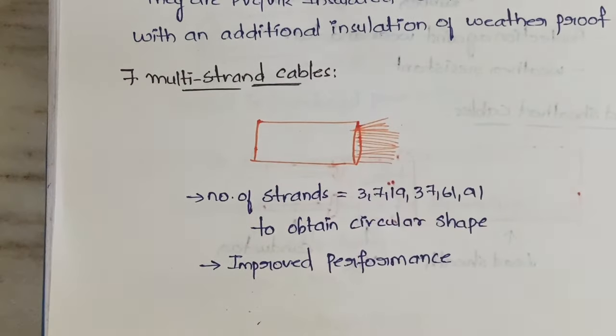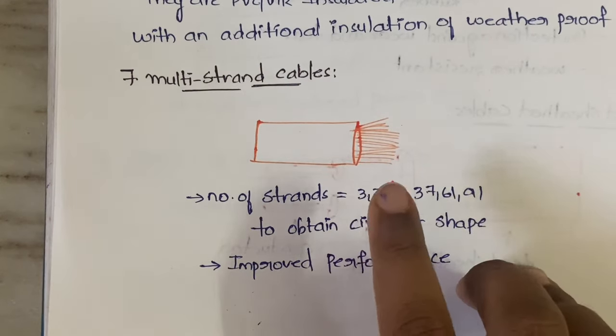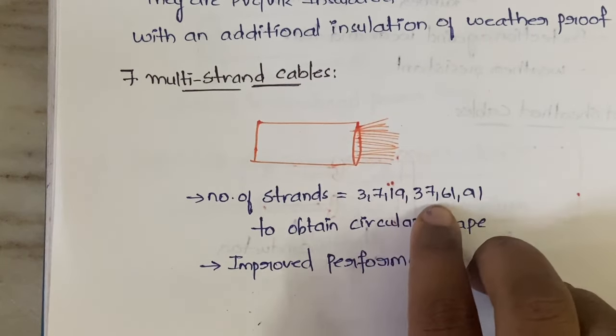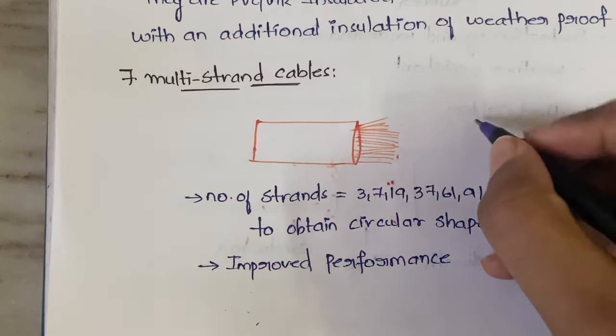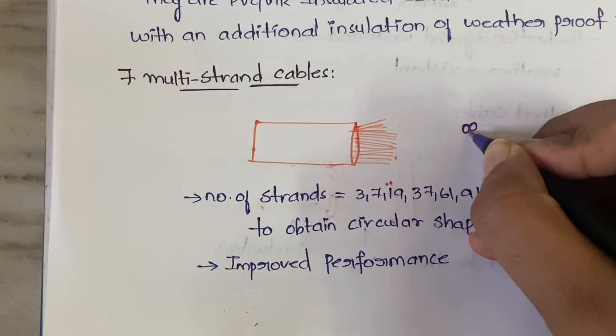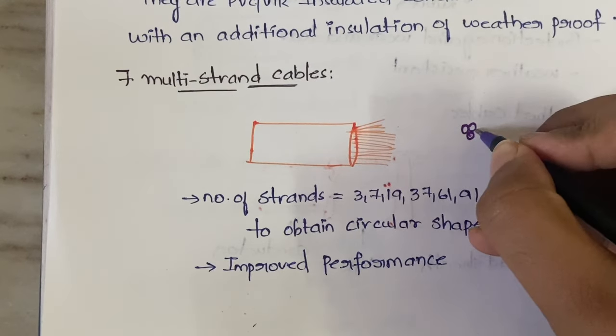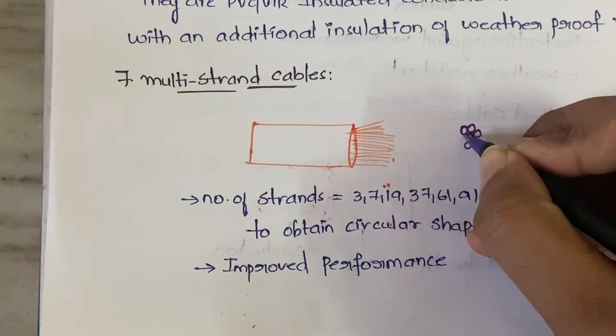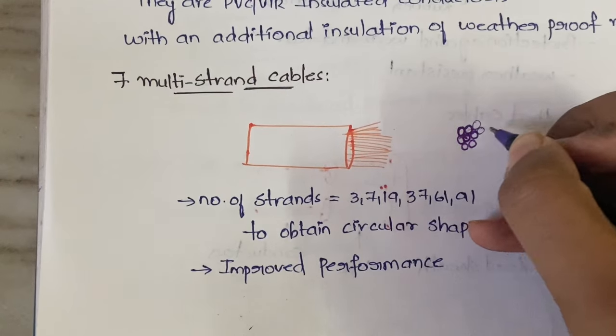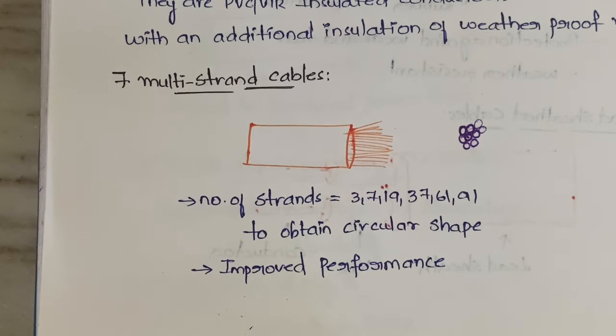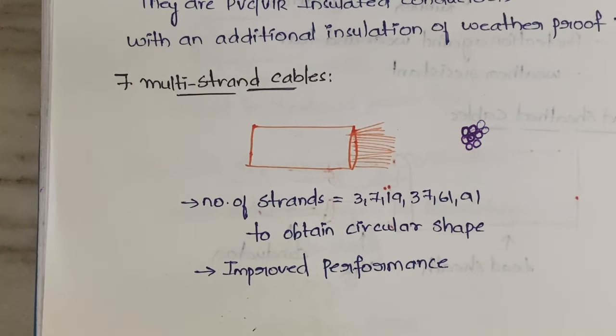The seventh type is multi-strand cable. In a multi-strand cable you will have multiple strands inside a single coating. These strands must be in fixed numbers — like 3, 7, 19, 37, 61, or 91 — because the goal is to obtain a circular shape. For example, 7 strands means 1 in the center and 6 around it. Following fixed numbers maintains the circular shape.